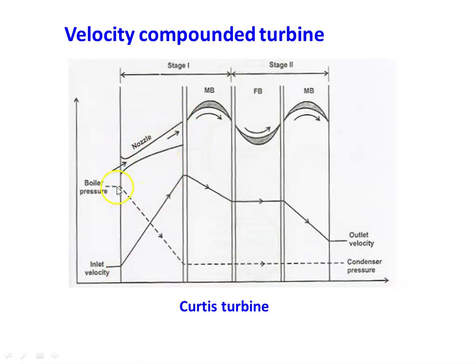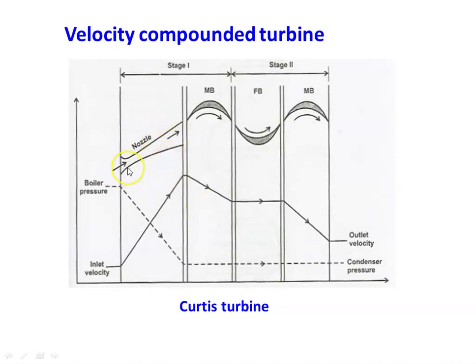The disadvantages of the velocity compounded turbine: since there is only one set of nozzles, the complete pressure drop takes place in a single nozzle, so that nozzle must be bigger and stronger to handle the complete pressure drop. Additionally, the outlet velocity from the turbine is also significantly higher, resulting in a loss of velocity energy at the turbine outlet.